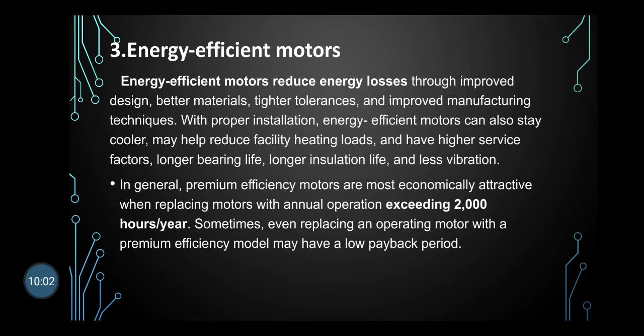Now, here the photo shows the energy efficient motor and how an energy efficient motor can be obtained by reducing the different losses. More copper wire of a larger diameter in the motor stator saves energy by reducing the resistance of the stator winding. Means by increasing the diameter of the stator winding, the resistance of that winding reduces, and by reducing the resistance we can reduce the copper losses of the stator winding.